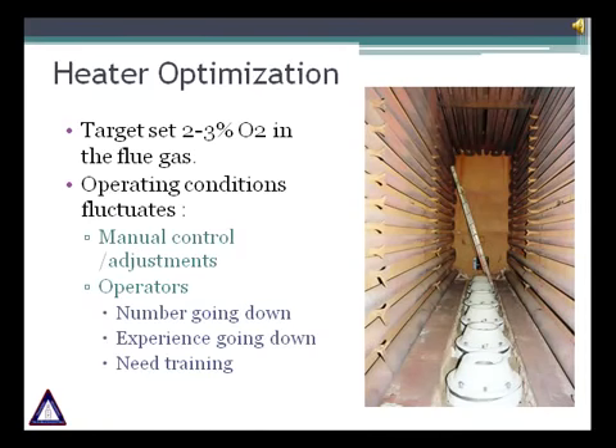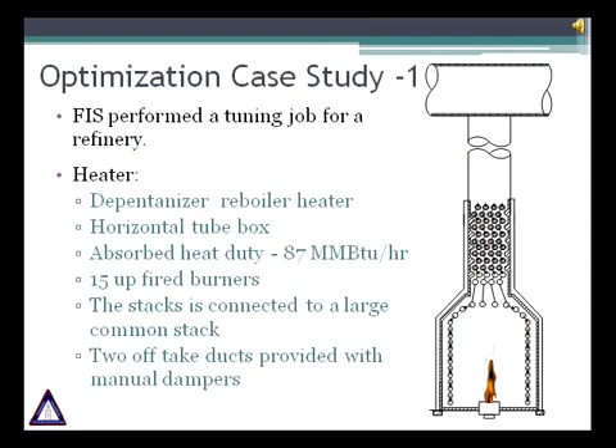As we saw in this presentation, optimizing fired heater performance is possible by making minor modifications and practicing good housekeeping. In the following slides we will demonstrate with examples how to increase the efficiency of a fired heater with minor modifications. A few months ago, our company had the opportunity to perform a tuning job for a refinery. The heater was a Depentanizer reboiler with horizontal tube box and 15 up-fired burners, two off-take ducts with manual dampers connected to a large common stack. The absorbed heat duty of this fired heater is about 87 mm BTU per hour.